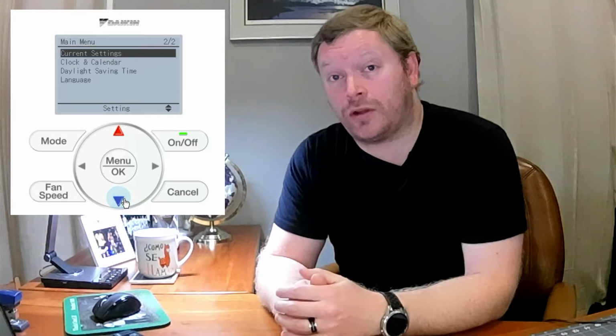When you click on current settings, it's going to give you all of the current settings that are programmed in the main menu. So your louver position, if you have an indoor unit with a louver, it's going to give you your schedule, enabled or disabled status, off timer, and whether or not it's enabled or disabled. It's also going to give you the current screen display configuration.